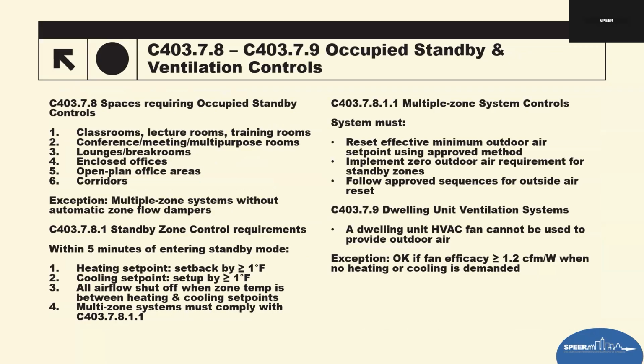And then we've got 403.7.8 to 9, occupied standby ventilation controls. That's now been expanded, which is one of the key energy saving control strategies of the 2024 IECC. These rules apply to many commercial spaces, and basically define exactly how the HVAC system should behave when rooms are unoccupied. Controls are being expanded from what was done in the 2021 code.